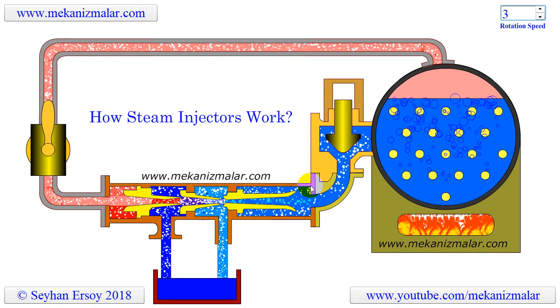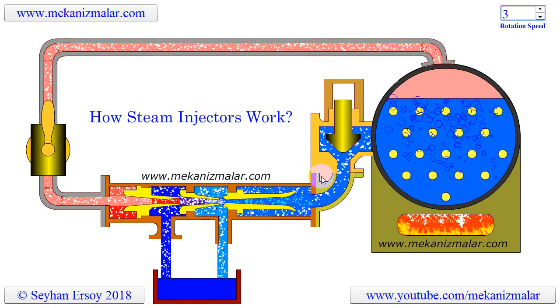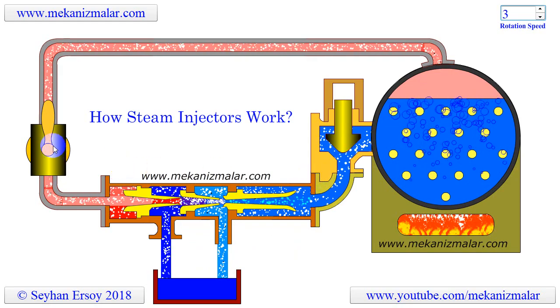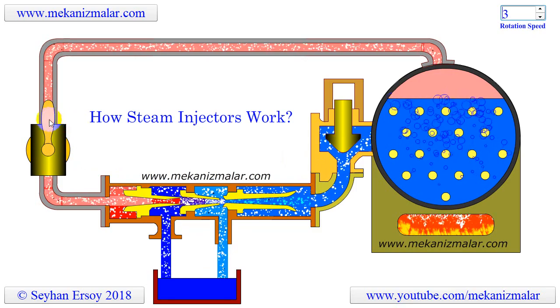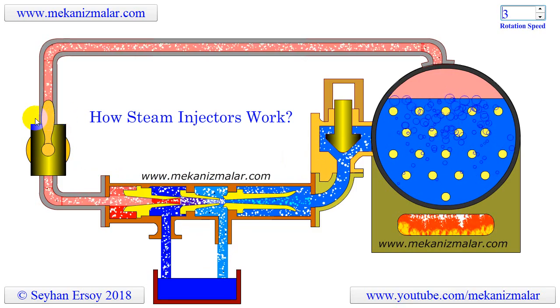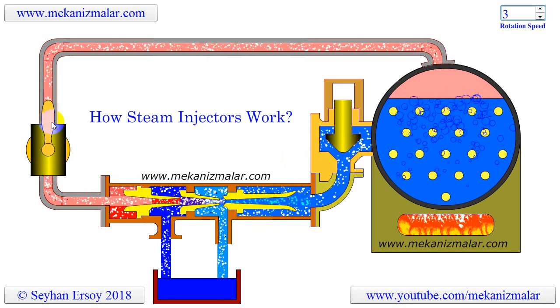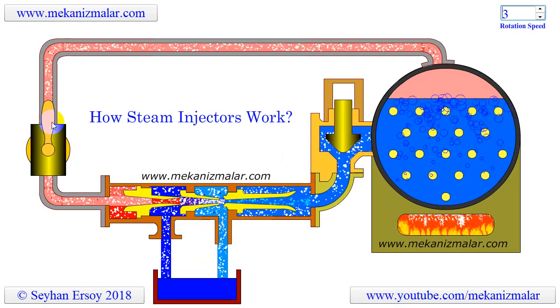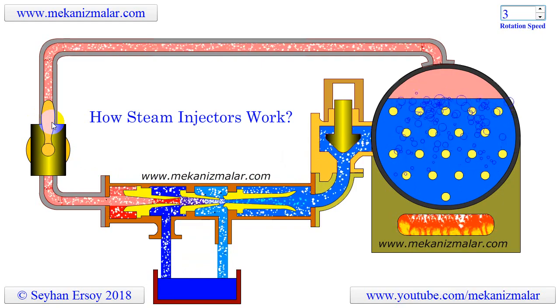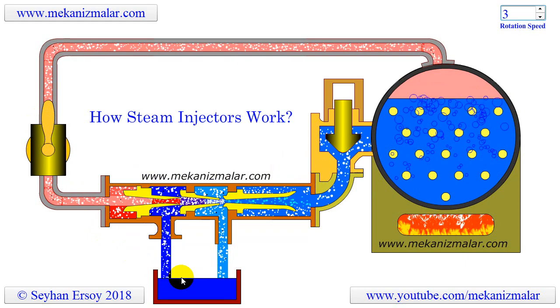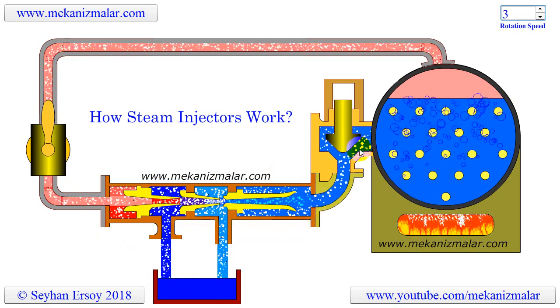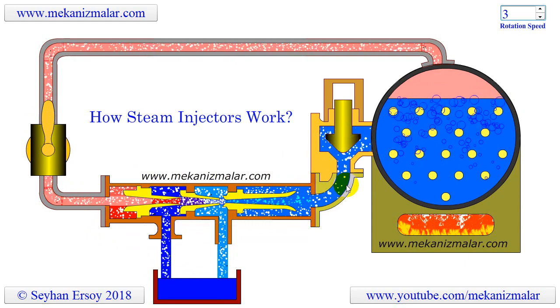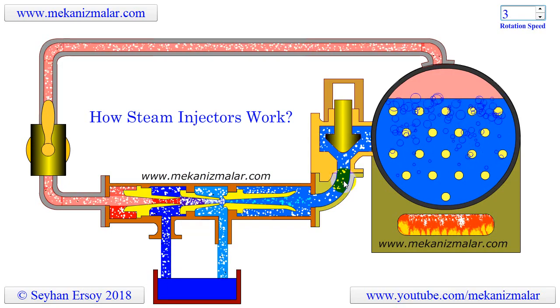The steam injector's operation will be interrupted by turning the valve, shown here, manually or automatically off. Turning off this valve will cut the steam flow to the injector, and in turn cause water flow from the reservoir to stop. During this time, the check valve, shown here, will prevent the boiler water from escaping to the reservoir.